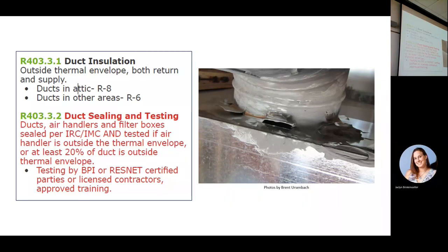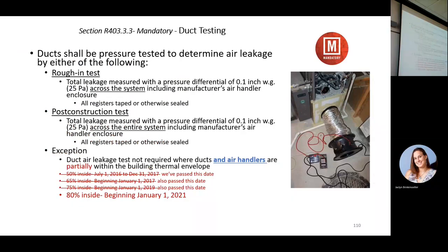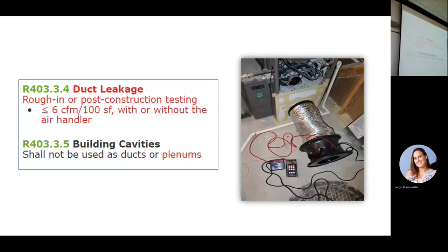Let's see, before we go too far, back up one more slide. Okay. Cavities. We were talking about making return airs out of ductwork, but I think that hasn't gone through yet, correct? Right. So with all this duct testing, the code without amendment says you're supposed to test it all. But if you're going to test all your ductwork, you can't pan joist because you'll never pass a test. Ever. I went on one, it was a nice house and the HVAC system looked pretty good. We didn't have enough horsepower in the fan to get the duct system to 25 pascals because all the wires and all the I joists are hard to seal up.